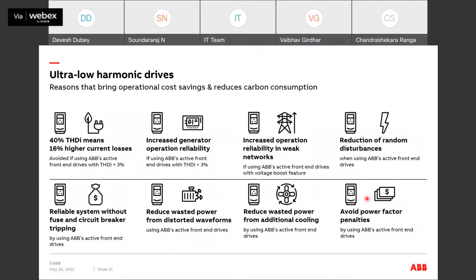Moving forward, now the point comes: how does this help to reduce carbon emissions? Any standard diode-based drive will have 40% THDi, which means 16% higher current losses. If we are using active front-end drives, it can come down to 3%. It also increases generator and operational reliability. If we are using active front-end drives, it can increase the operational reliability in weak networks.